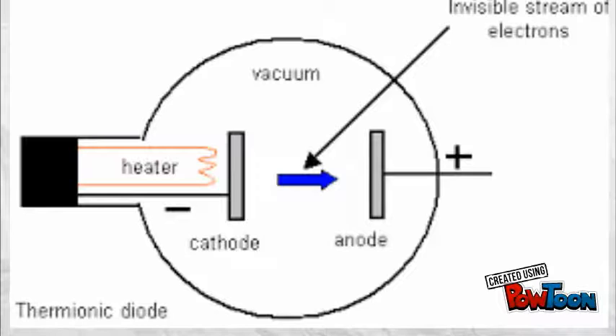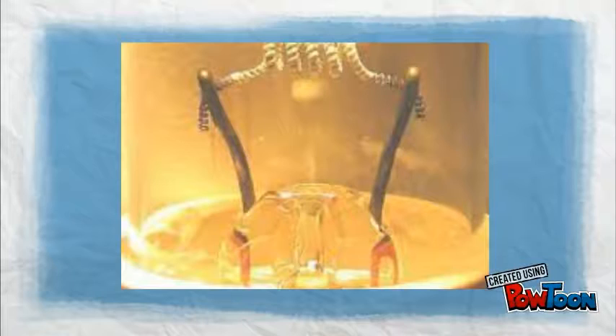Thermionic emission is the emission of electrons from a heated metal, which is the filament, on the cathode side of the x-ray tube. The cathode has its filament circuit that supplies it with the necessary filament current to heat it up.